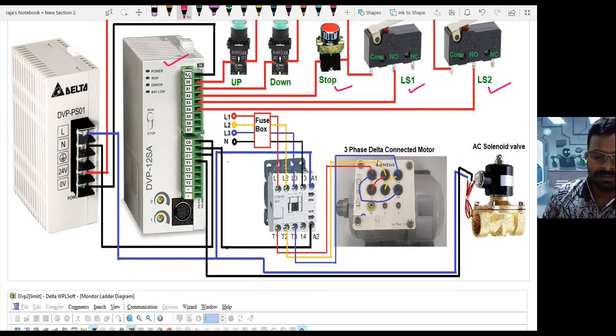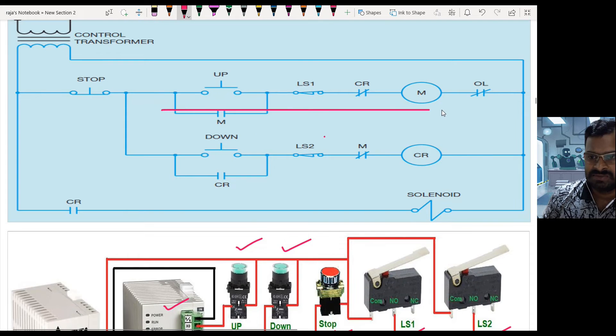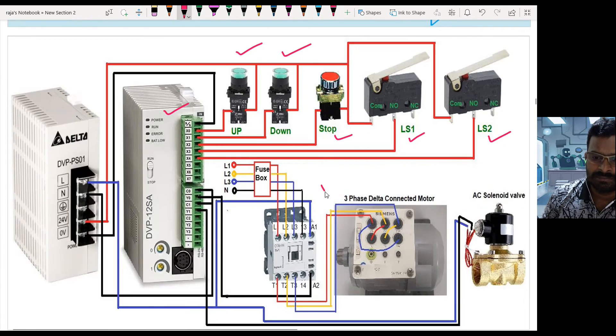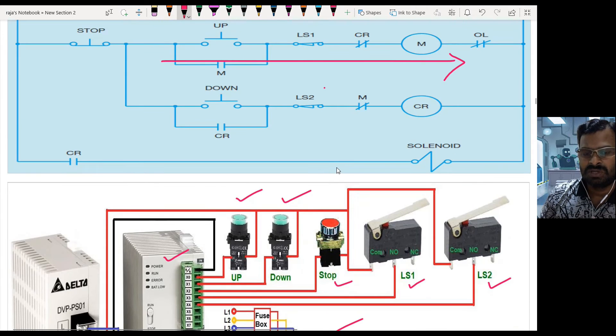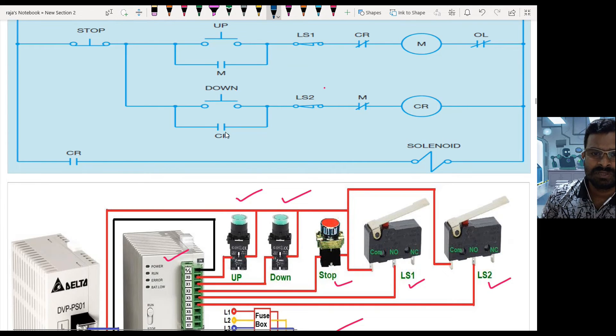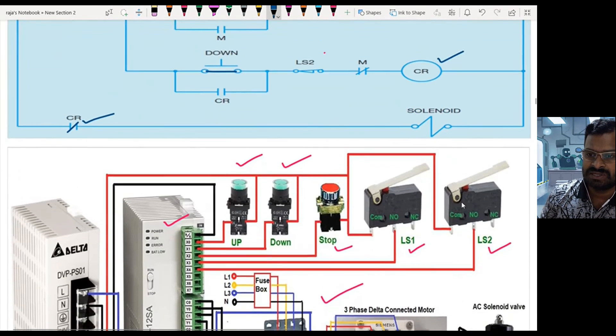When the conditions are satisfied in the ladder, the motor is enabled through the contactor. The PLC gives output at Y0 so the contactor closes, power is transferred to the motor coupled to the pump, and fluid flow makes the cylinder go up. When it reaches the upper position, LS1 breaks the circuit. When the operator presses the down switch, the control relay energizes, its contact closes, and the solenoid gets energized.